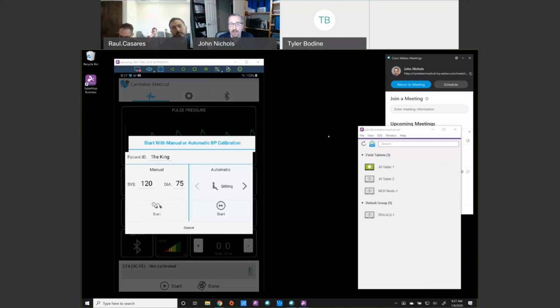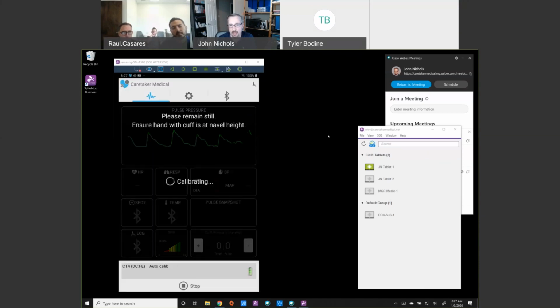You won't have to enter the patient ID again, and then you just hit start under automatic. Again, at navel height, still and quiet, and I'll explain to you what's going on the screen. What you're going to see is pulses and then a flat line. And what you're going to feel during the flat line is the pressure of the cuff increasing, Raul. And then the pulses are when the caretaker is listening for the signal.